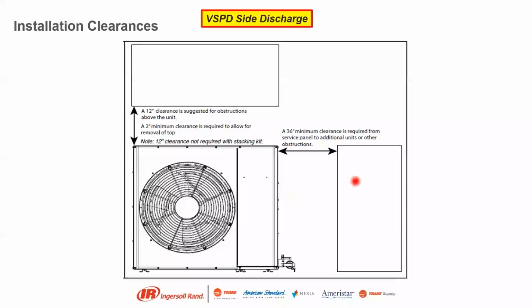Again, we want 3 feet. I've gone out on site visits where we have a wall right there. We're not able to get that access. So we want a 36-inch minimum to that electrical. You got your compressor in there and everything. So keep that in mind when placing these units, and 12-inch clearance above it, 2-inch minimum.